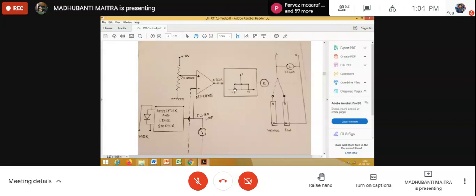Or we can think about H on, 1 or 0, or even we can think of the relay. Relay is switching. Either the relay is getting energized or the relay is getting de-energized. That's why the name of the experiment, or typically we call this kind of control scheme the on-off control scheme. And here, since we are trying to control the temperature of a plant, the name of the experiment is on-off temperature control system.